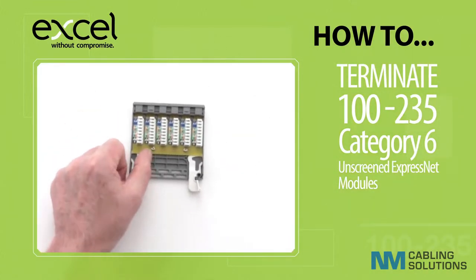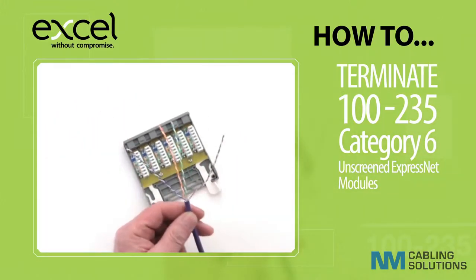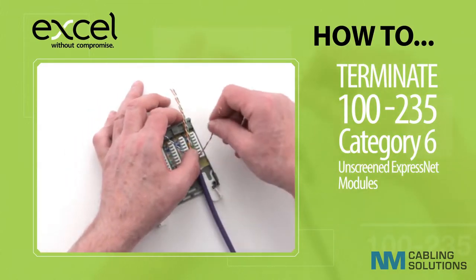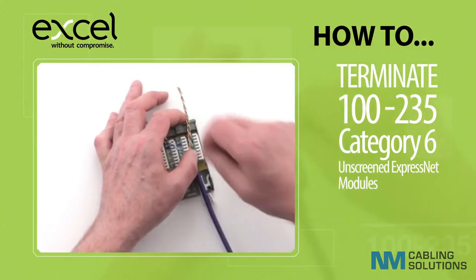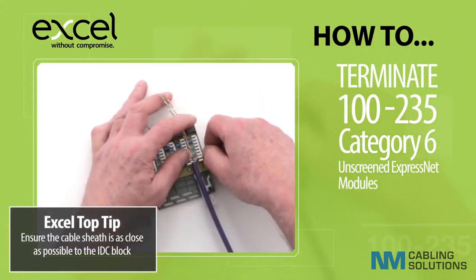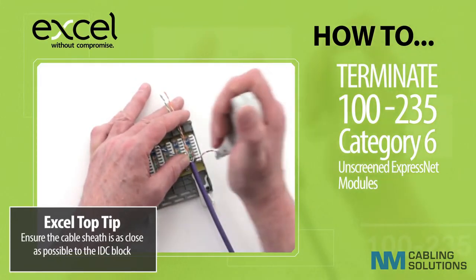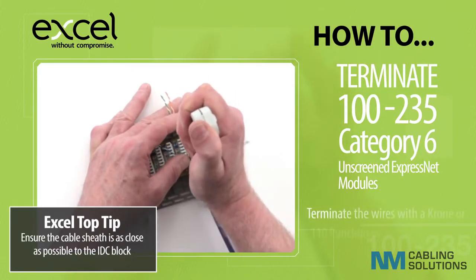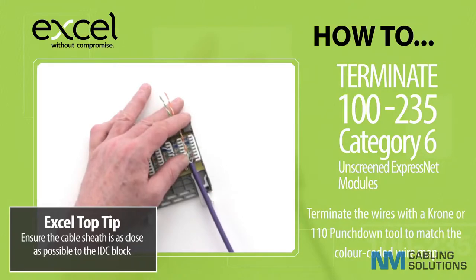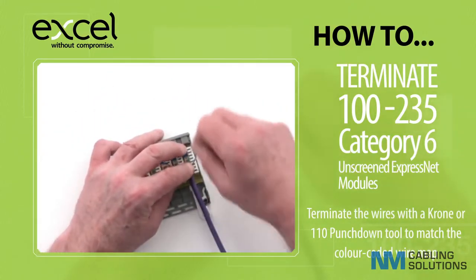Next, we will install the cabling into the module. When terminating the cable, ensure the outer sheath is as close as possible to the IDC block. Then, using either a krone or a 110 punch-down tool, terminate the wires according to the wire map inside the module.